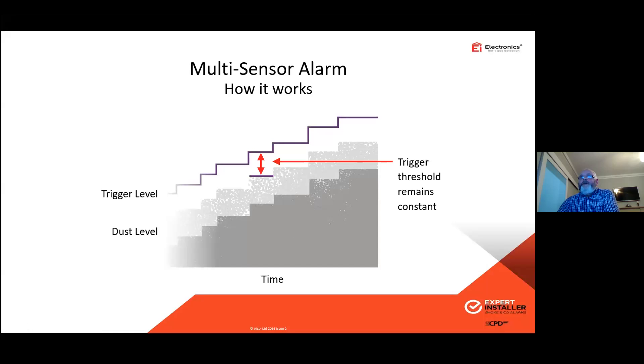We also have what we call dust compensation built into the device. Some smoke alarms can give a lot of trouble over time with dust ingress — a unit goes on the ceiling and has to last for the next 10 years with very little maintenance. In this device we have built-in dust compensation. The thresholds have to remain constant — those purple lines on the graphic represent your threshold. If they're not constantly maintained and dust builds up, once it gets closer to the top level the unit goes into alarm. So if the bottom layer goes closer to the top layer by introducing dust into the chamber, the top layer then steps up. That would happen 32 times over the life of the unit — a major advance on that type of technology.